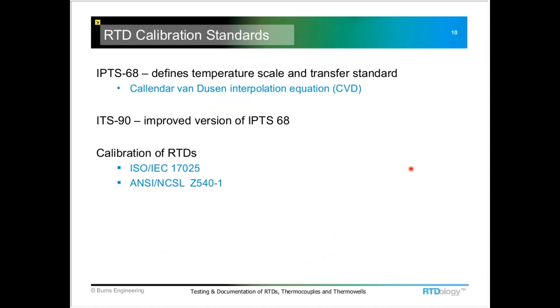In addition to this Callendar-Van Dusen or CVD equation, there's an improved version that was done in 1990. The advent of a little more computing power made it possible to get a better interpolation of the resistance versus temperature characteristics between the actual calibration points. It's mostly used for laboratory standards, not so much in the industrial grade. Most of the transmitters and other equipment will have the capability of doing this Callendar-Van Dusen interpolation. The higher end readouts and other devices for doing a calibration will be able to do it with these ITS-90 coefficients.